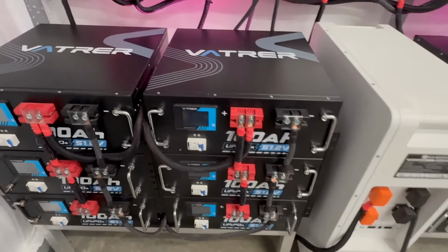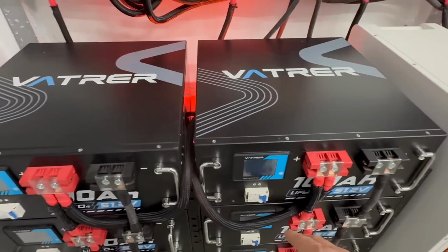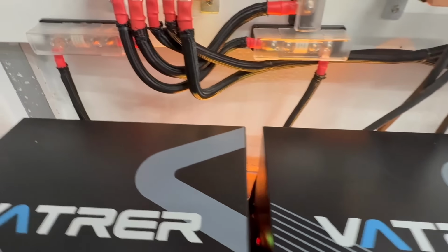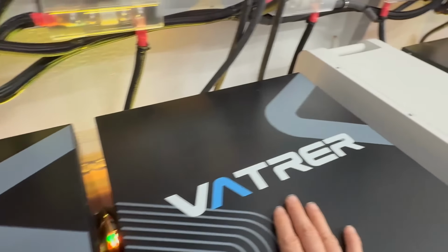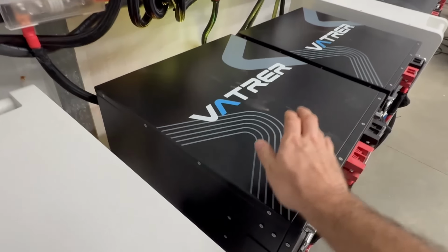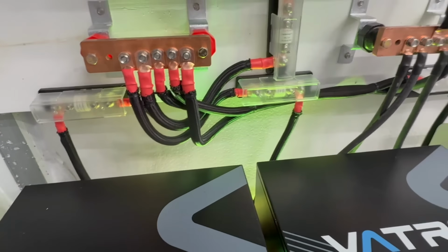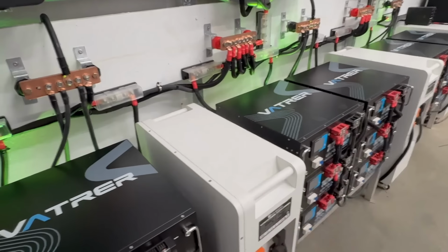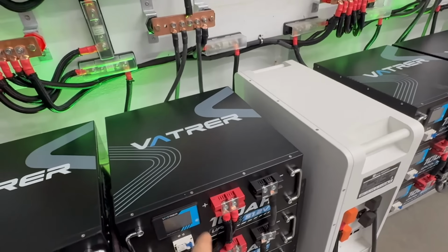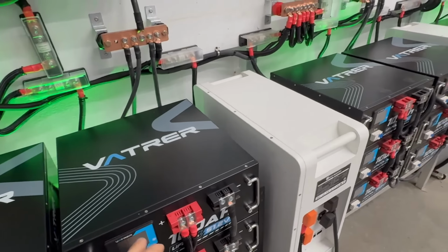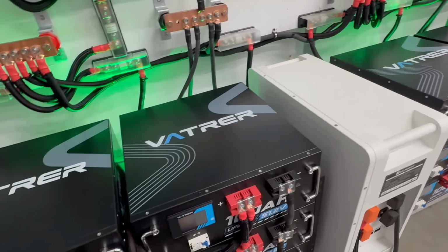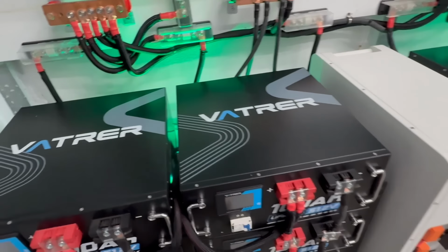So back to this: you have your 2-aught cable going up, and each one of these has their own T-class fuse. The reason for that is, as you're connecting all these batteries together, you do not want a shorted BMS causing an inrush from all the other batteries. That would be very, very bad.